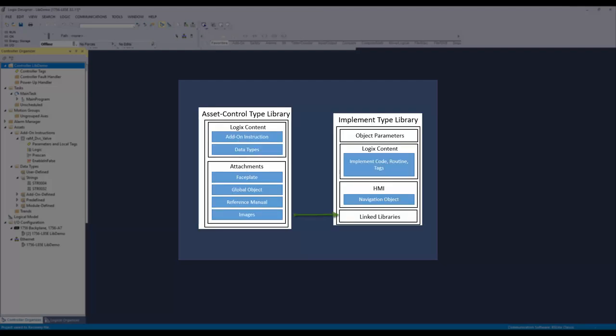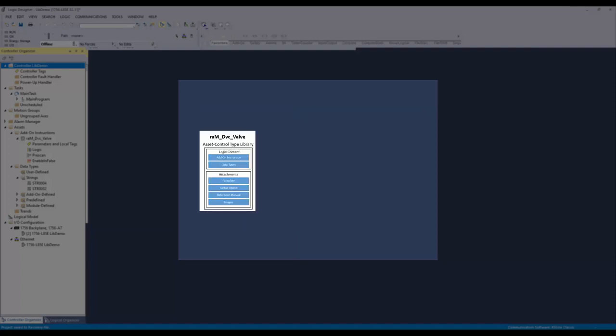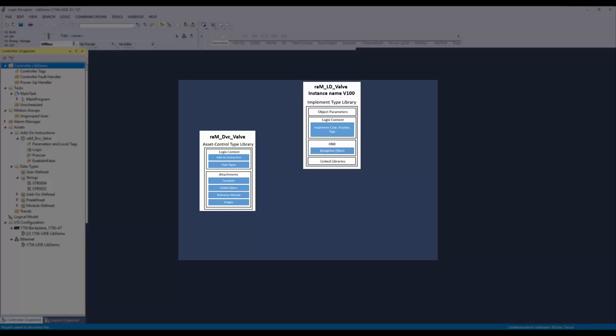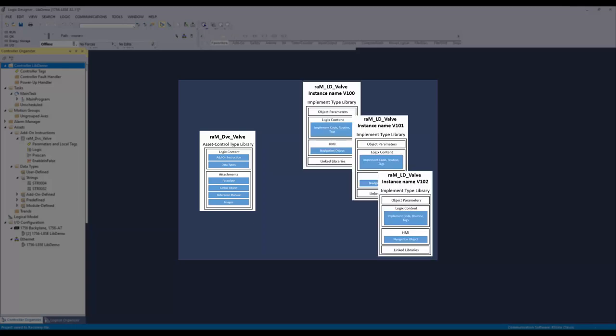An implement type library contains implementation code of the addon instruction and HMI implementation like navigation button. The asset type library is linked to the implement library as link libraries. In ACM, the user can choose to instantiate only the asset library or both implement and asset library. While instantiating in a project, an asset library is required to be instantiated only once, whereas the implement library can be instantiated depending on the number of instances of implementation required in the project.